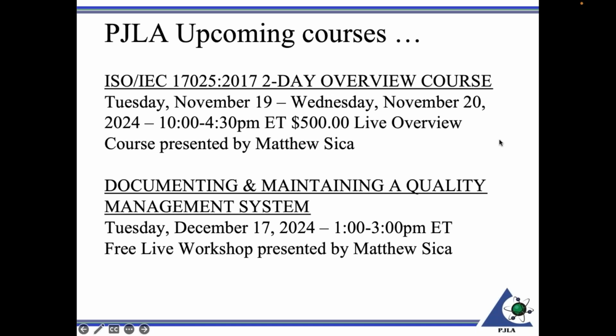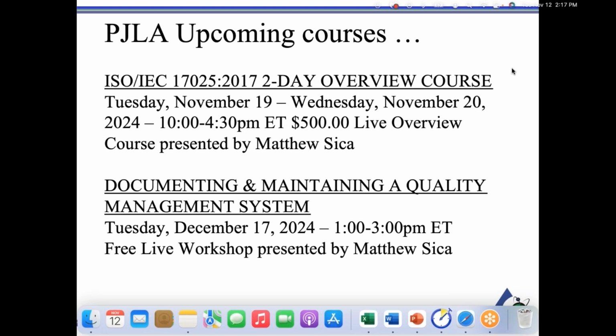I'm going to go ahead and answer this first question that came in. Are you able to send me the PT schedule documents? I believe what it's being referred to is the LF81 form. That is available if you go to our website, pjlabs.com, and go under resources or under PT. You can download the LF81 form and utilize that to make your PT schedule. Like Doug said, you don't have to use that form if you have your own, but have something that looks similar to that, to ensure you're meeting the PJLA PO1 requirements for frequency.